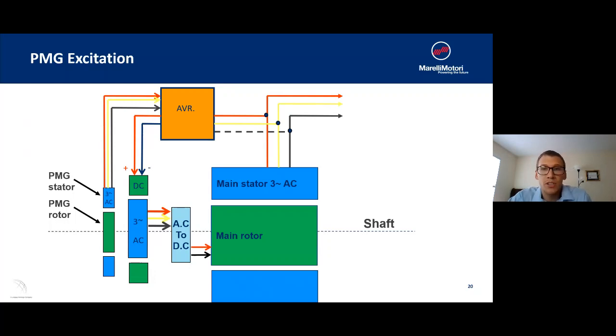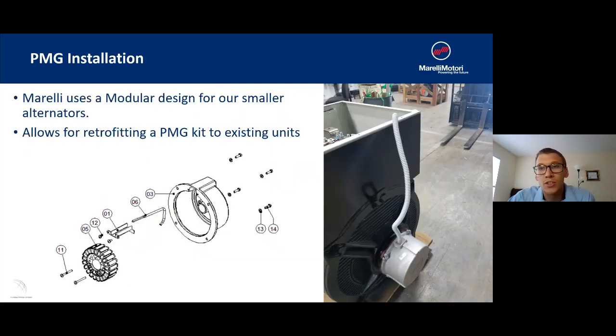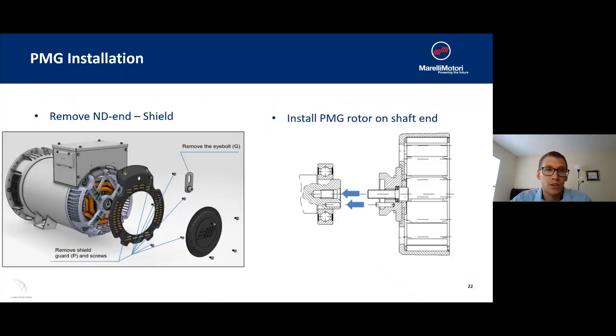For Marelli, our PMGs are a pretty easy install for our smaller units. We use a very modular design for our alternators, which allows you to retrofit a PMG kit to any of your existing units. If we look here at the breakdown of our PMG kit, it's just a few parts that we're going to bolt on to the end of the alternator. This picture on the right here is going to be what it looks like once it's installed. To install one of our PMG kits, all we're going to have to do is remove the non-drive-end shield of the generator, which is just held on with a few bolts, and install the PMG onto the rotor shaft ends where there's slots already installed on the shaft for the PMG.